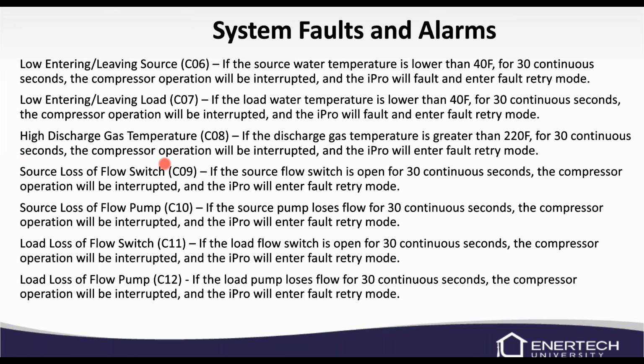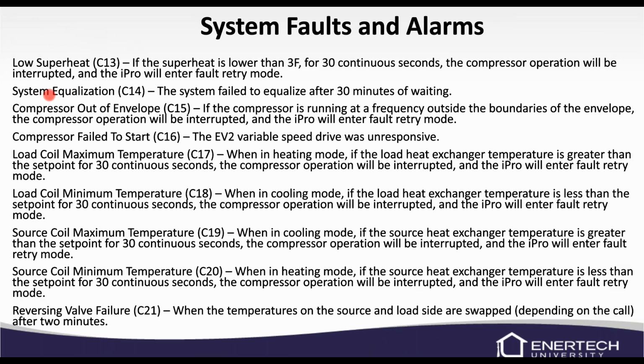discharge gas temperatures, source loss of flow switch, source loss of flow pump, load loss of flow switch, load loss of flow pump. The pump ones are feedback, and the switches are just that, it's a paddle switch in the circuit. But it'll tell you even if the system didn't equalize, low superheat, reversing valve failure, things like that. So again, it'll list all these different faults for you.